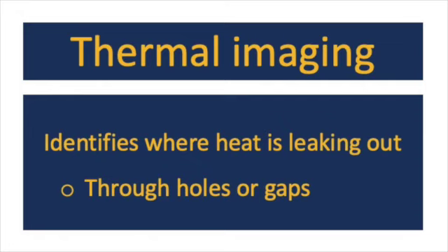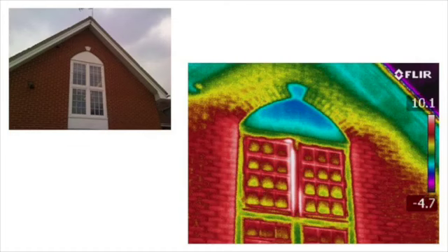First of all then, let's look at some thermal images which show heat escaping due to holes and gaps. We're going to show you some examples of heat leaking out of windows due to gaps that weren't easy to spot with the human eye. For example, this is a thermal image of a wooden window that was actually closed, but the white vertical area shows where heat is leaking out. This gap wasn't visible to the human eye.